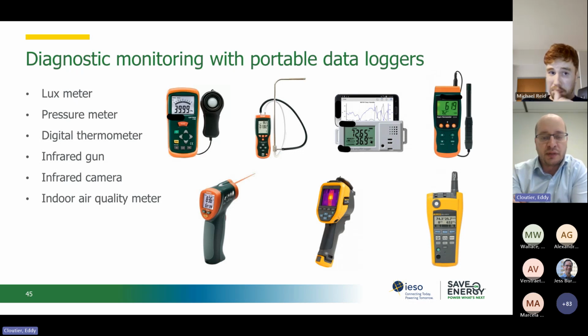An indoor air quality meter can allow you to see if there are indoor air quality problems in some area, or I would say the opposite. If everywhere in your building you have very low CO2 levels, it might be an indication that the air intake is more than sufficient, or too much outside air intake. So it might show you that there's a problem with the outside air intake.